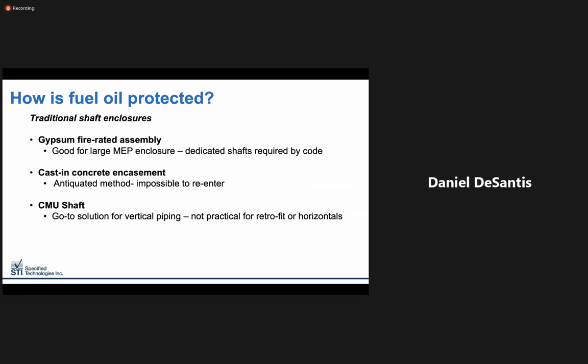We currently protect fuel oil piping in a number of different ways. Gypsum wallboard assemblies are great for large MEP shafts, but since fuel oil requires dedicated shafts, space and access can become an issue. Cast in place encasement, much like with electrical circuitry, is an acceptable method but seldom used due to its weight and inability to re-enter once cured. CMU shafts are commonly used for long vertical runs between floors because they're relatively inexpensive and provide reliable protection. But that's not really practical for horizontal offsets or for retrofit applications.